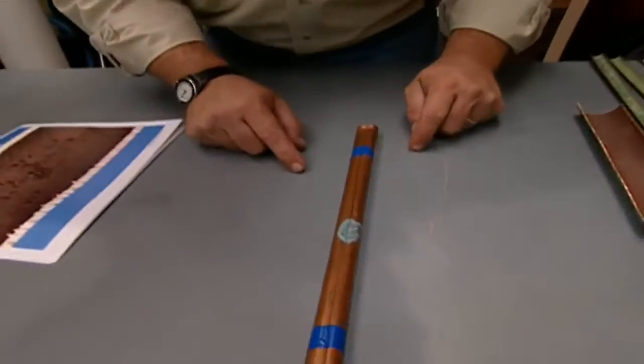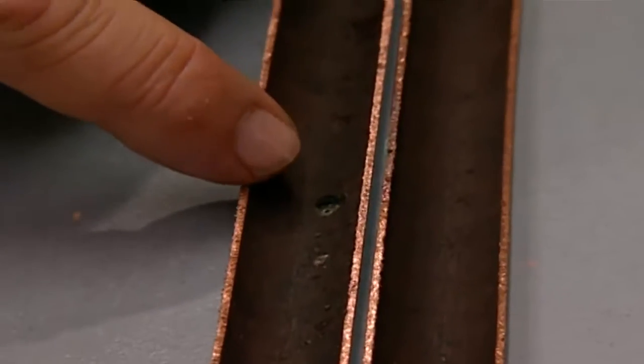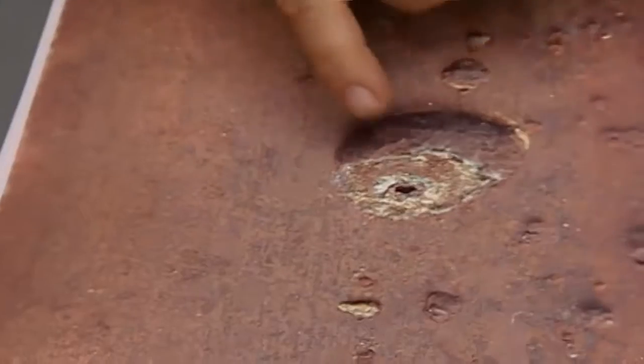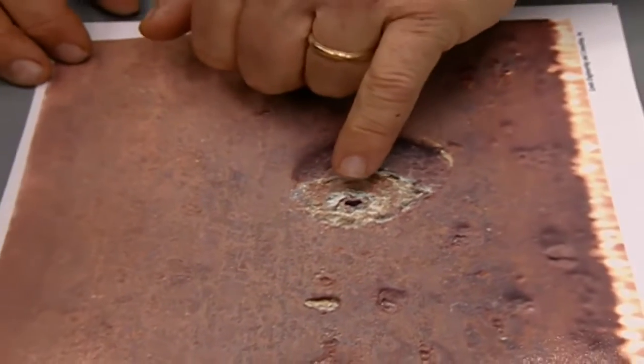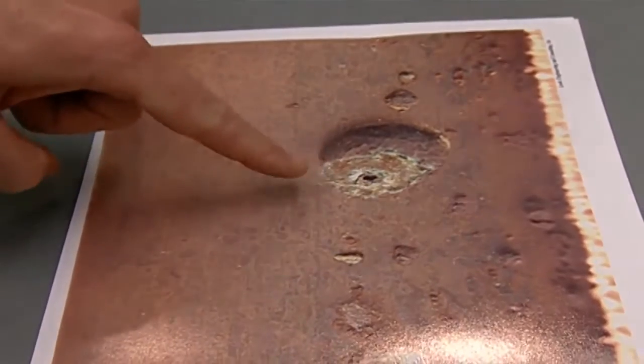Here's a piece of the hot water pipe that we cut out. You can see the corrosion point on the outside. When the pipe is split, we see a nodule right here of corrosion, and that was in a variety of places. Under a high-powered microscope, here are the images that we see. You can see one of the nodules. When that nodule is broken apart, you can see there's a pit corrosion point, and there was the presence of iron underneath it. The corrosion builds up around that little flake of iron.